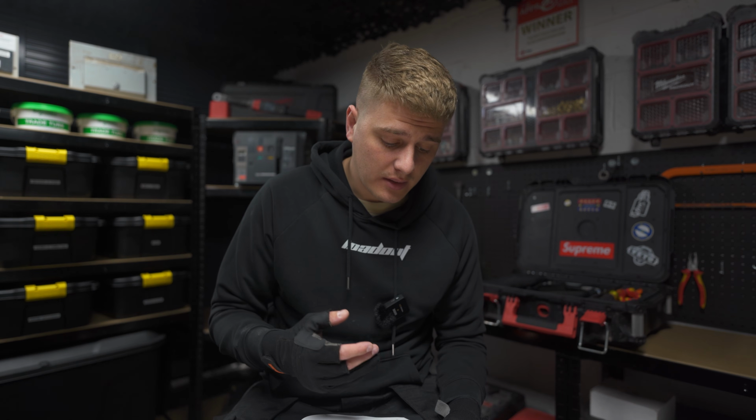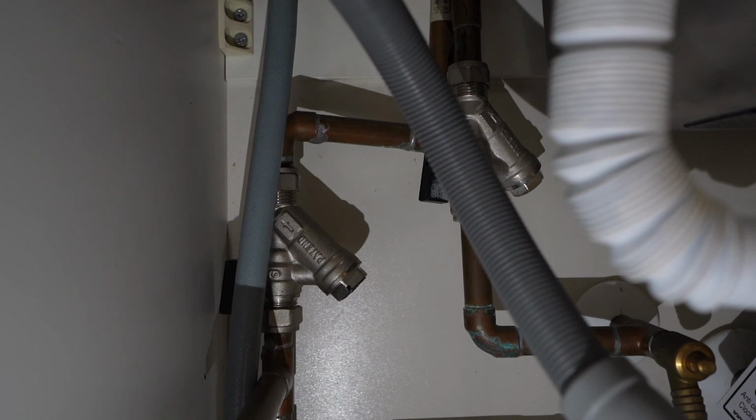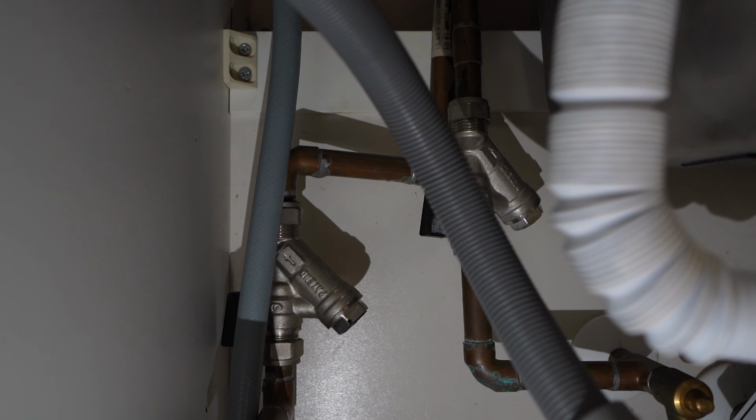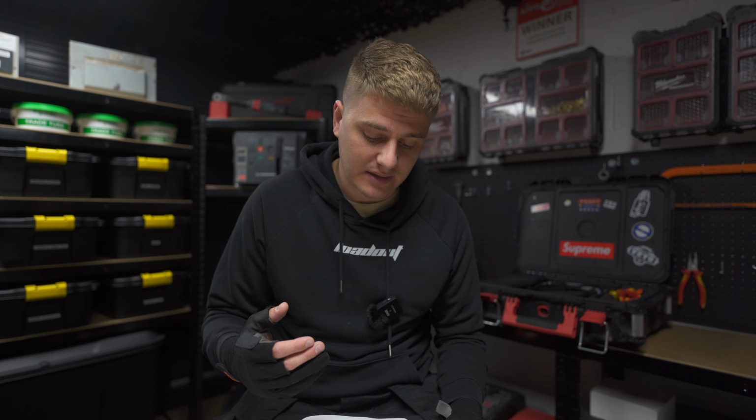There's also a note that states where non-metallic pipes, for example plastic, enter a building and are connected to the metallic pipes within the building, metallic pipes within the building do not normally require protective bonding as they are unlikely to be extraneous conductive parts.